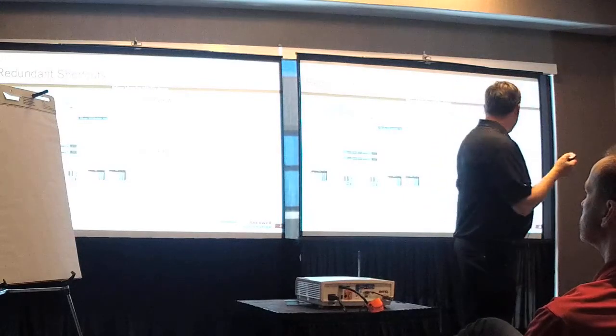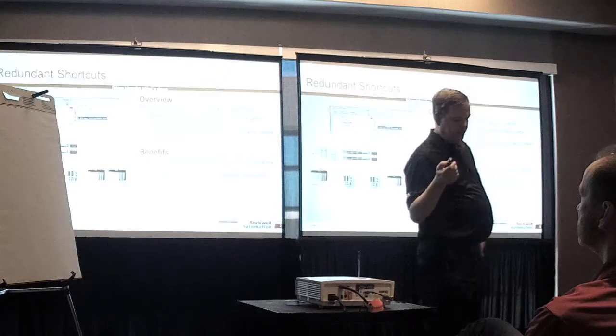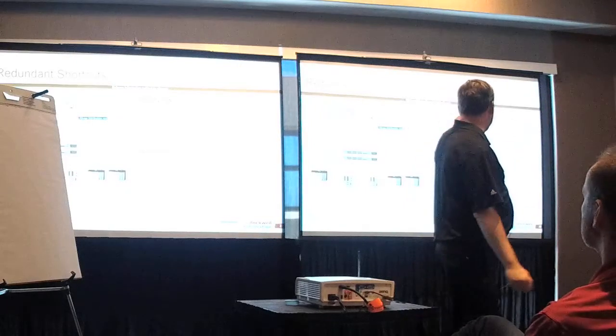So we're taking first just the communication between the data servers and the controllers. You talk about things like blind time reduction when I have a switchover. How do I empower better communication so that if LAN 1 or LAN 2 goes down, I still have full functionality? Because we had done things like teaming of NICs and so forth. Again, I'm dangerous enough to say something, but not the expert, if you will. That ability to have fully redundant networks, not only from, say, the servers to the controllers, but also from the controllers to the I/O now, with a parallel redundancy protocol.